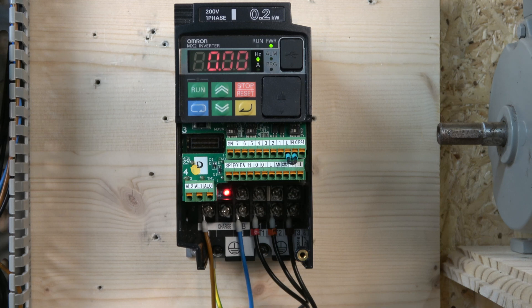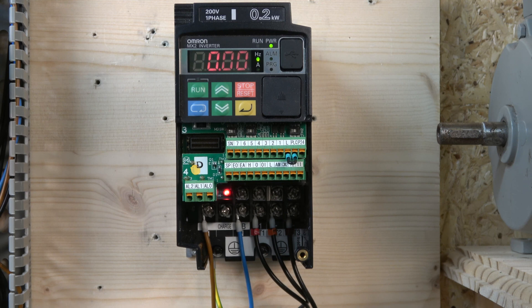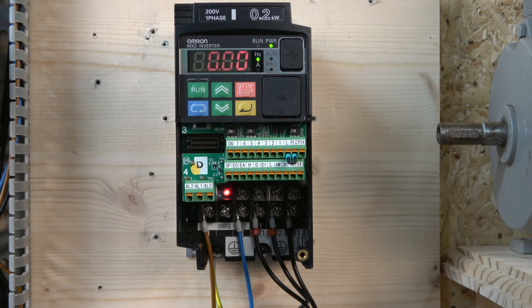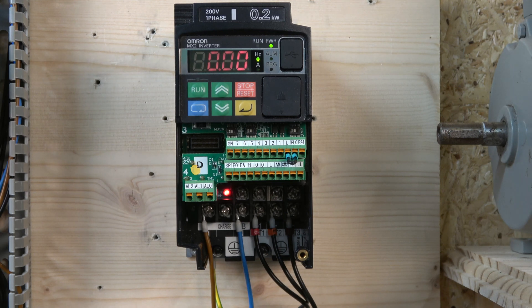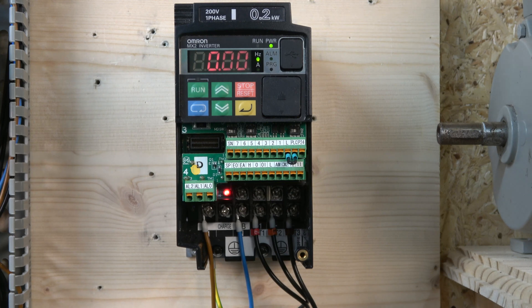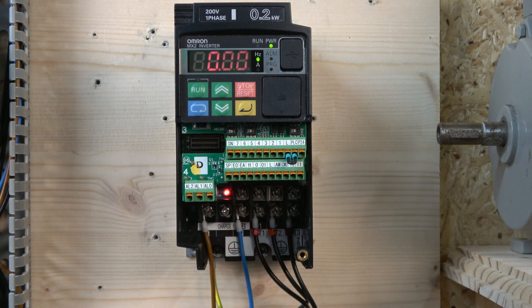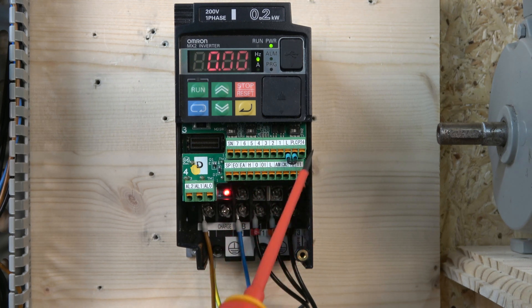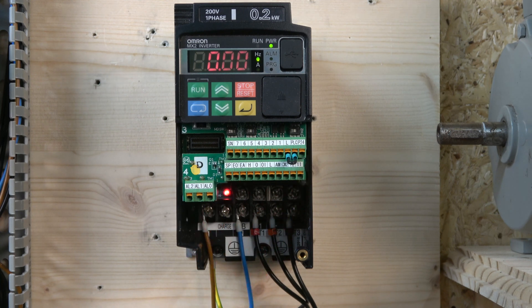Between L, PLC, and P24 is where you can select what source or what sort of connection you're using - sink or source. We're going to be using source, so we're going to leave L and PLC linked out and use 24V to power off all our inputs.